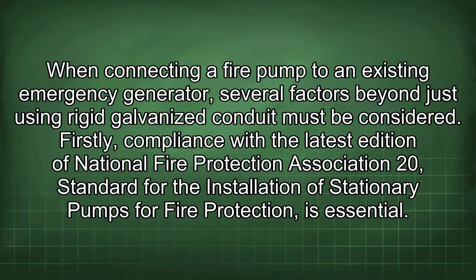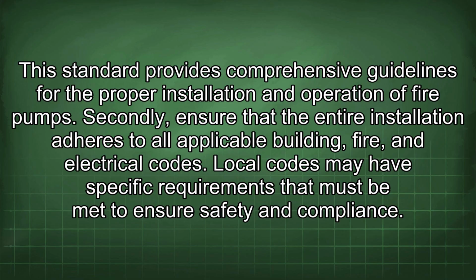When connecting a fire pump to an existing emergency generator, several factors beyond just using rigid galvanized conduit must be considered. Firstly, compliance with the latest edition of National Fire Protection Association 20, the standard for the installation of stationary pumps for fire protection, is essential. This standard provides comprehensive guidelines for the proper installation and operation of fire pumps.